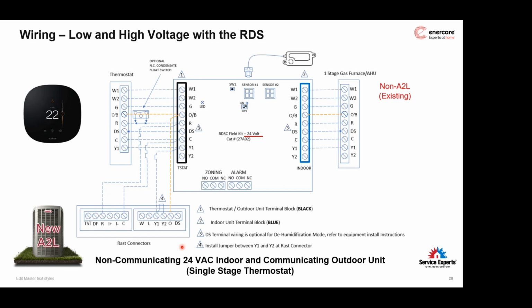So it's important that we wire to that O terminal with a heat pump on the control board in the furnace. The other thing here, of course, is defrost. If we're deciding to temper the defrost for our customer, Betty White doesn't like feeling air conditioning in the heating season coming up, because during a defrost call, we would wire the W wire from the outdoor unit up to this control board as pictured. I don't know what you're reading or watching this on, but the W wire is in green, at least the way I've shown it here, so that you can see it.